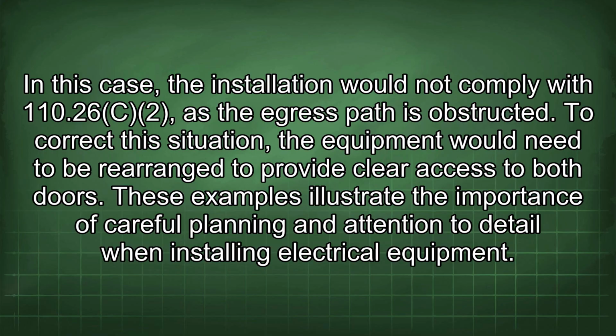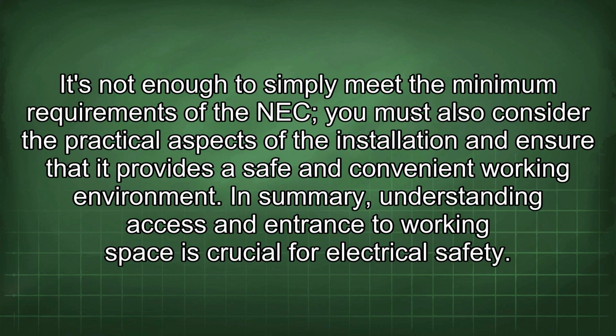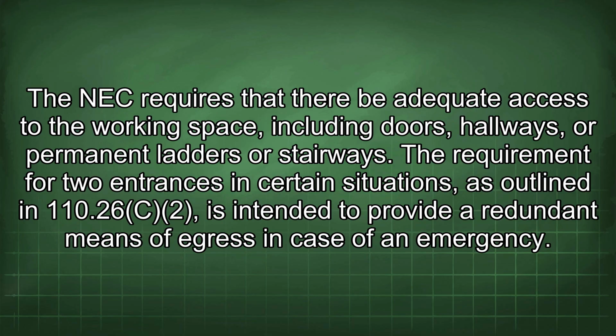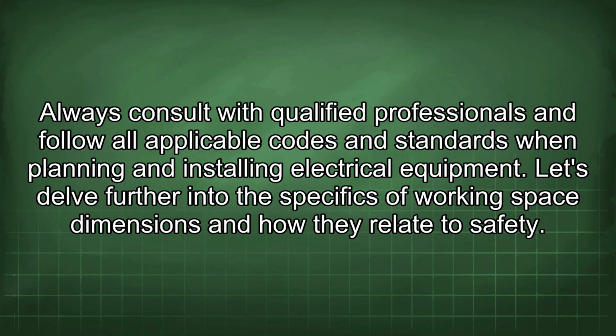These examples illustrate the importance of careful planning and attention to detail when installing electrical equipment. It's not enough to simply meet the minimum requirements of the NEC, you must also consider the practical aspects of the installation and ensure that it provides a safe and convenient working environment. In summary, understanding access and entrance to working space is crucial for electrical safety. The NEC requires that there be adequate access to the working space, including doors, hallways, or permanent ladders or stairways. The requirement for 2 entrances in certain situations, as outlined in 110.26(C)(2), is intended to provide a redundant means of egress in case of an emergency. Always consult with qualified professionals and follow all applicable codes and standards when planning and installing electrical equipment.